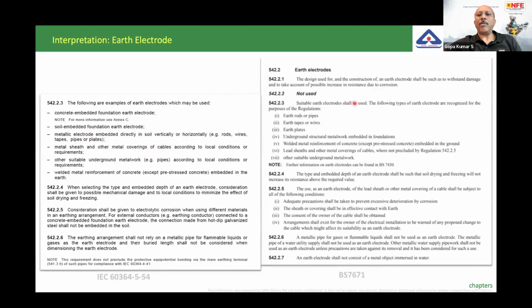But you see here, suitable earth electrodes shall be used. The following types of earth electrodes are recognized for the purpose of the regulation. Now, the sequence has changed. It talks about earth rod or pipe, earth tape or wires, earth plates, underground metal structure work embedded in foundation. That means whatever is put first in IEC is here sequence number 3. Welded metal reinforcement of concrete, which you can already see in the IEC, is the same thing. Basically, the same subject is followed here, but you can see here earth rod or pipe, earth tape or wires, earth plates. So the serial numbers 1, 2, and 3 are definitely going to confuse the users.